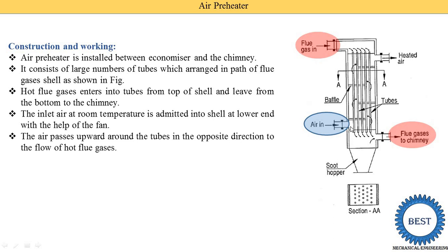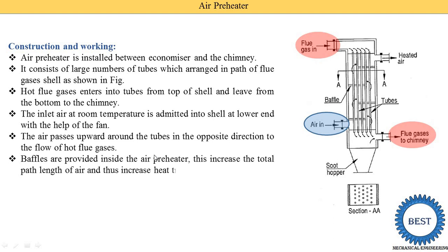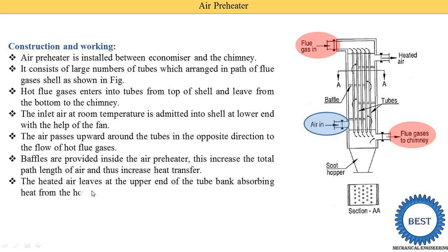The air passes upward around the tubes in the opposite direction to the flow of hot flue gases — flue gases move from top to bottom, while air moves from bottom to top, making it a counter-flow arrangement. Baffles are provided inside the air preheater to increase the total path length of the air, which increases heat transfer. The heated air then leaves from the upper end of the tube bank after absorbing heat from the hot flue gases, and is supplied to the boiler.